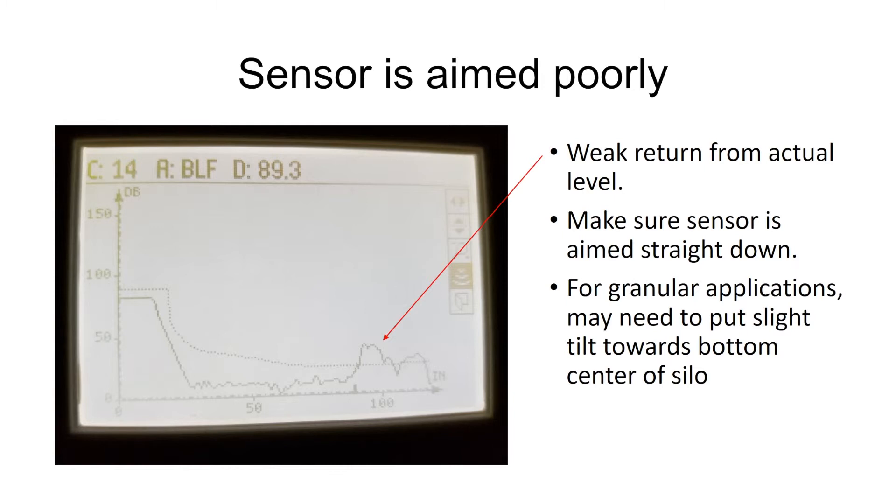Now, if you are using ultrasonics for granular level, you may want to have the sensor pointed a little bit towards the bottom center of the silo so that the reflection we get is more normal to the granular product. But for liquid applications, you definitely want to have it pointed straight down.